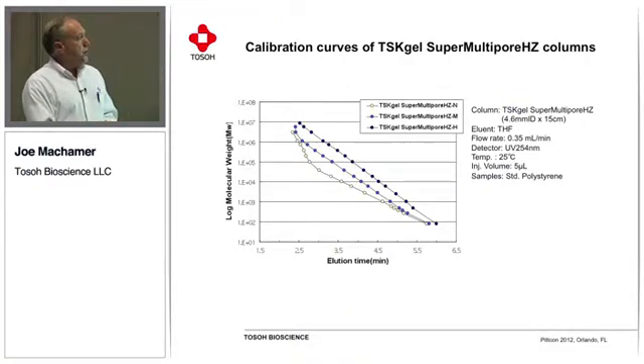This is 3 calibration curves showing the 3 different materials that we have. So the material here, the N material, is the 3 micron, and then we have the 4 micron in the M, and the 6 micron is the H. So we're getting a very wide useful range, and if you're looking for the oligomer region or smaller polymers, then the N material is giving very good resolution.